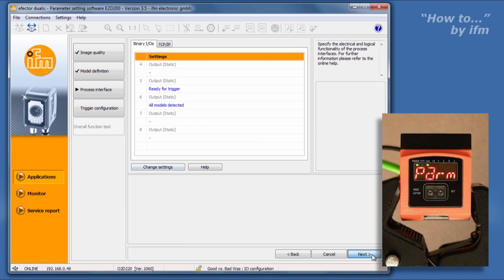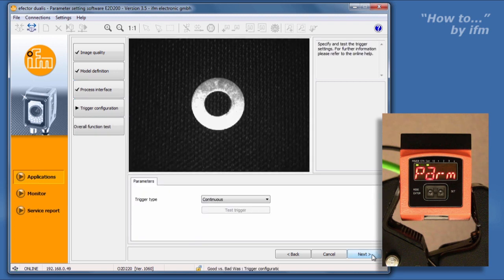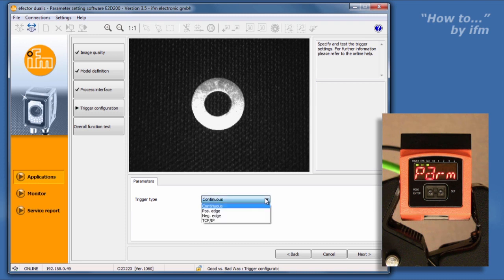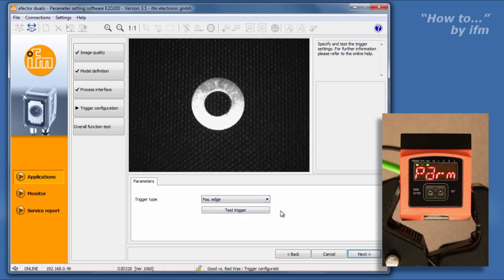Click Next to accept the default settings, and we can move on to set up the trigger. The trigger, usually either a photo eye or a PLC, will tell your O2D when to take an exposure. Under Trigger Type, we will select Positive Edge, meaning that a photo eye will trigger the O2D when an object first comes into the photo eye's sensing area, as opposed to Negative Edge, which would trigger the O2D when an object leaves the sensing area.